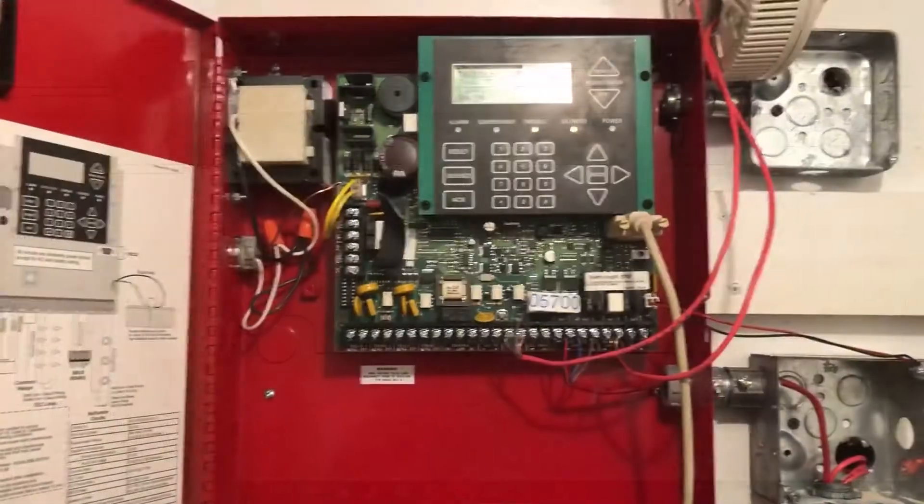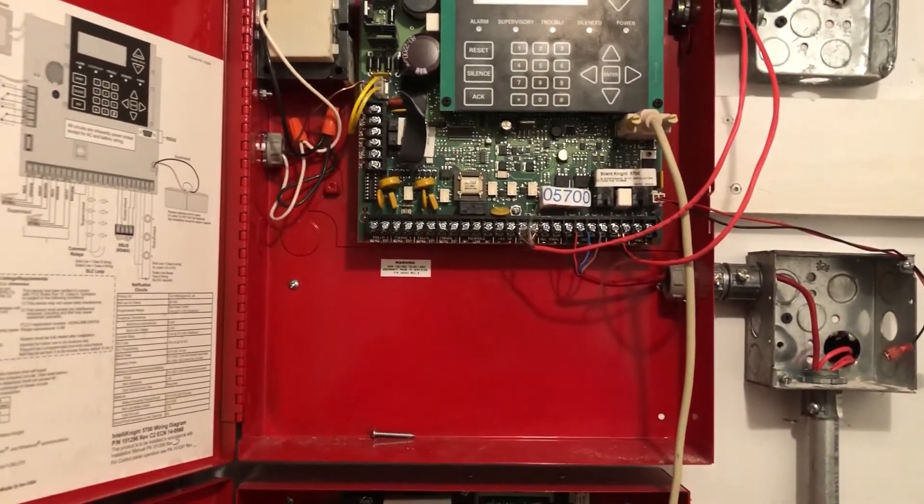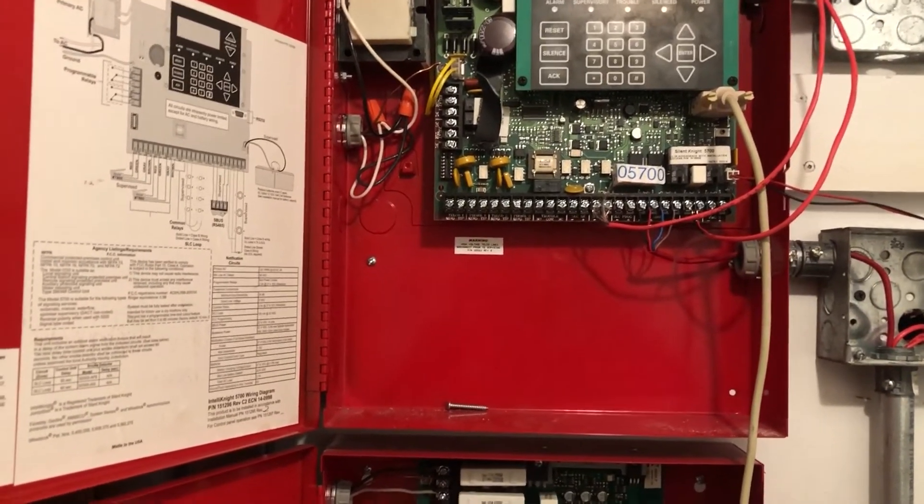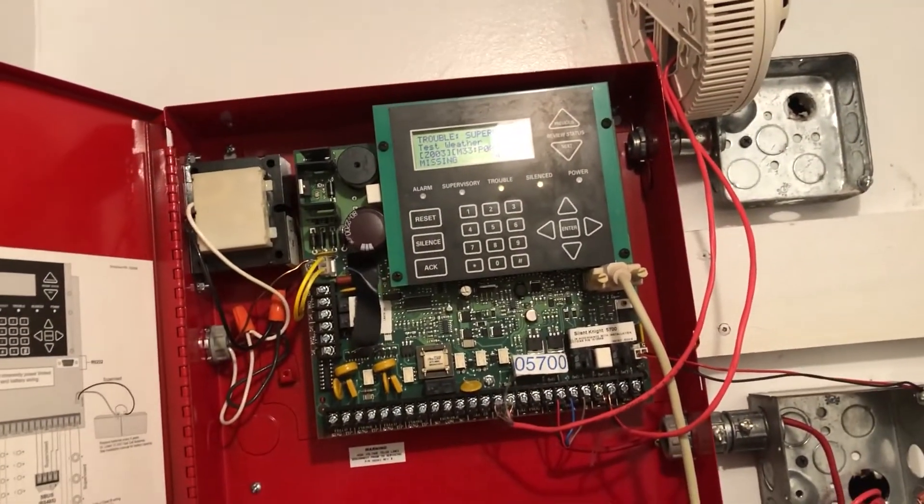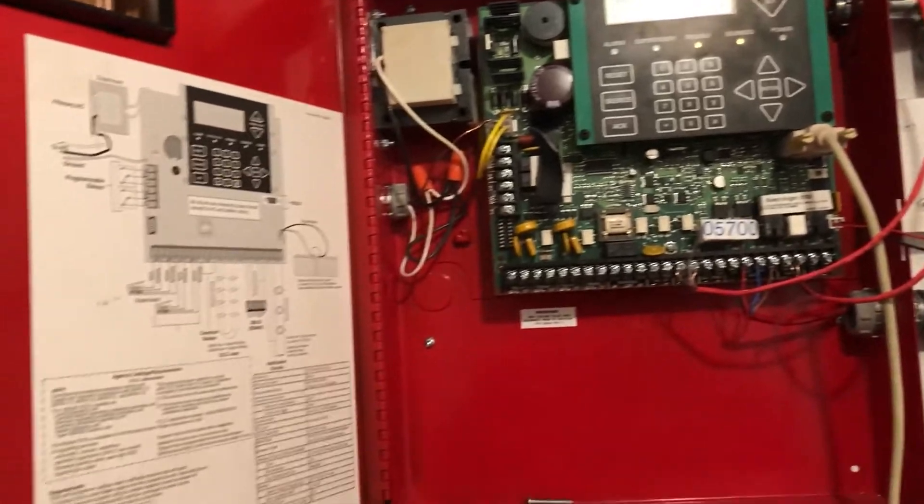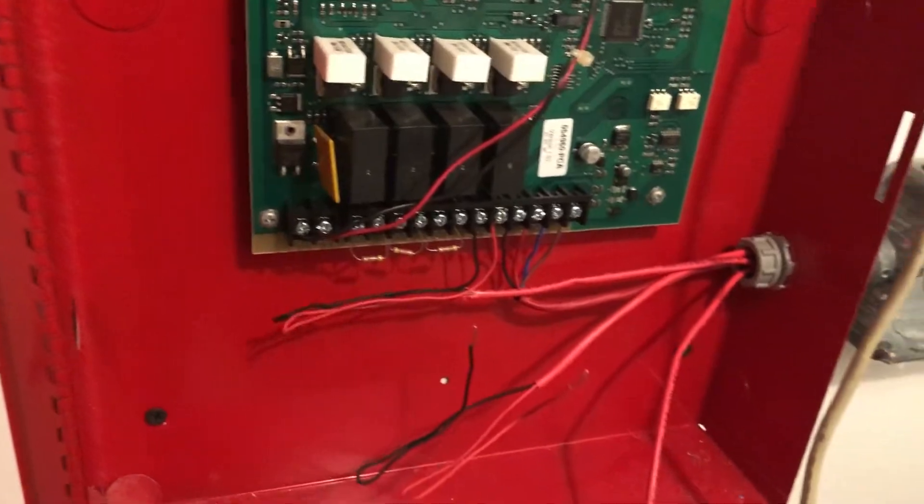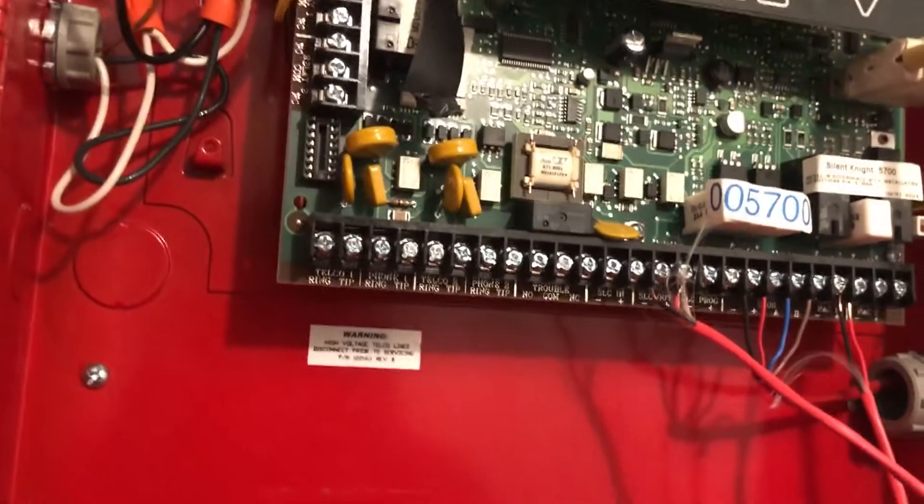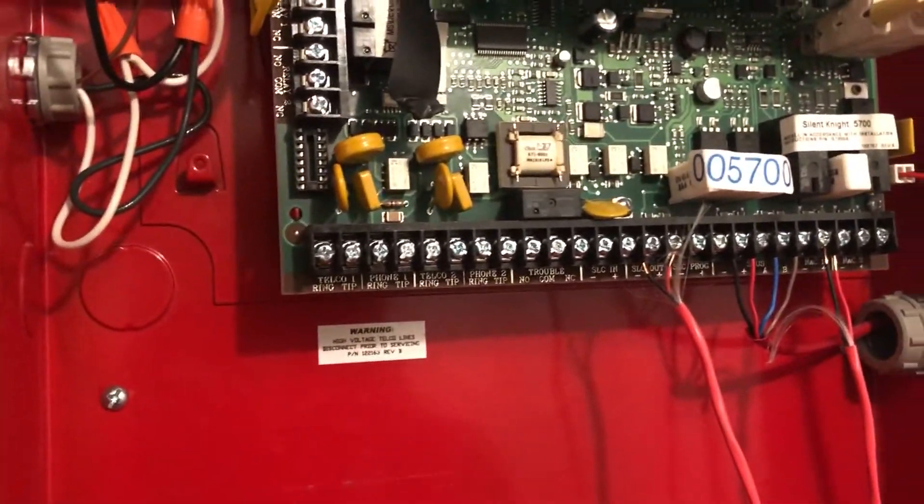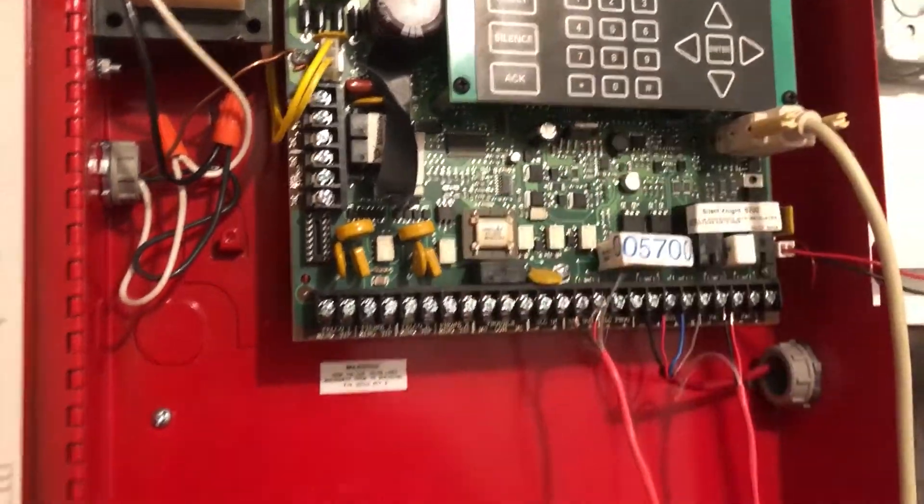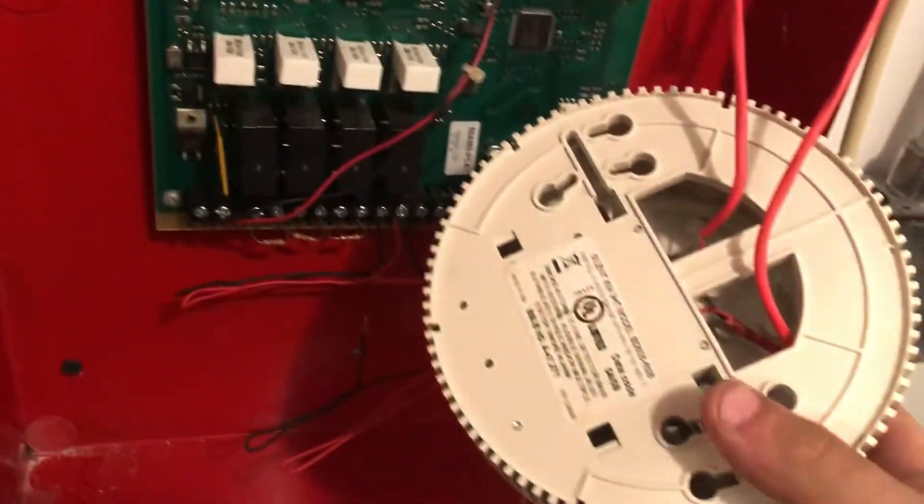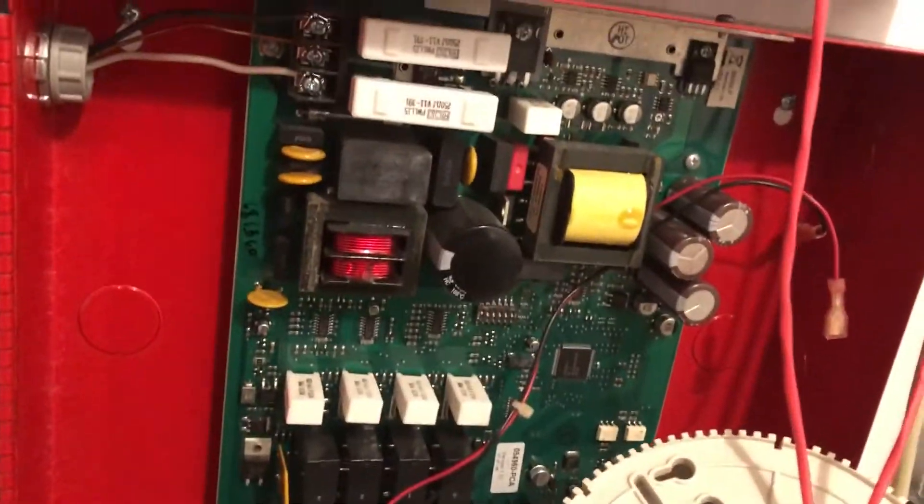So we're back at the panel now. The programming has been successfully downloaded to the panel. It will beep when I go into programming, so please excuse that. So it's a little bit of a mess right now but we have the one hooked up that we talked about. This goes out to a fire alarm in this section. One thing I forgot to mention is that you have to make sure you have one of the available 24 volt outputs set to constant power because that's how the base is powered. SLC is just control.